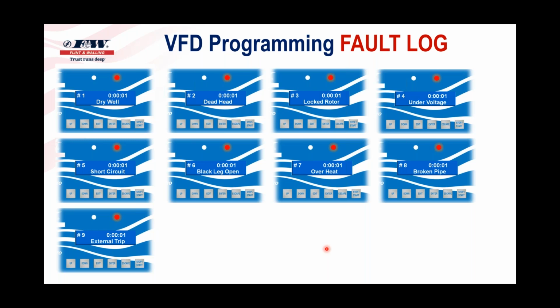We've got applications in livestock where if it's poultry, turkeys, hogs, and they're out of water, they want to know, and they want to know now. So they may have lights or a horn or any number of things can be wired into these drives. Liquid level controls, lightning arresters. So there's any number of external devices or components that can be wired into the drive. And if one of those goes awry, that's the kind of message you're going to get. It's going to say it's an external trip.